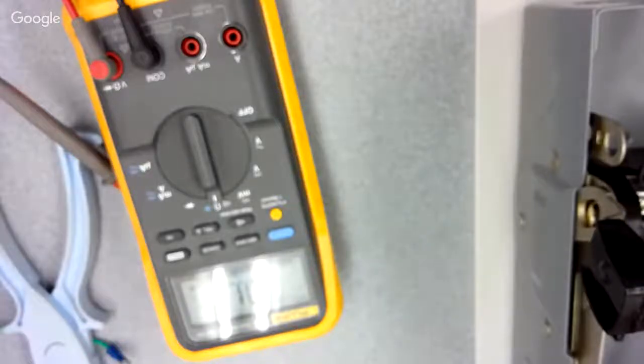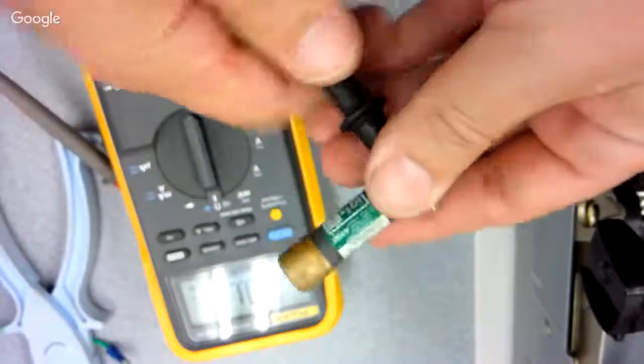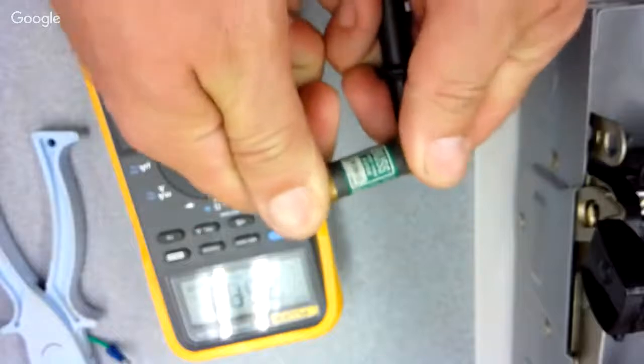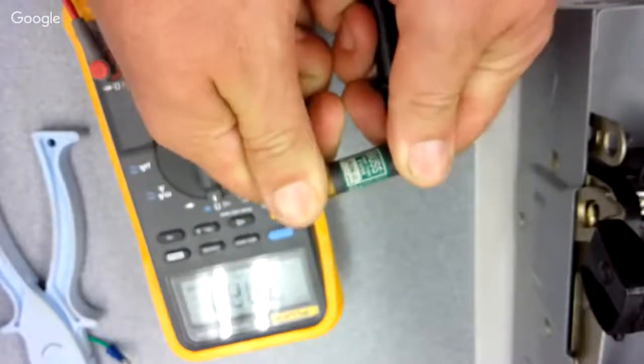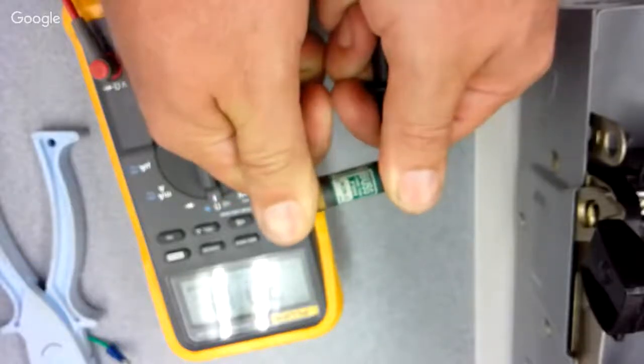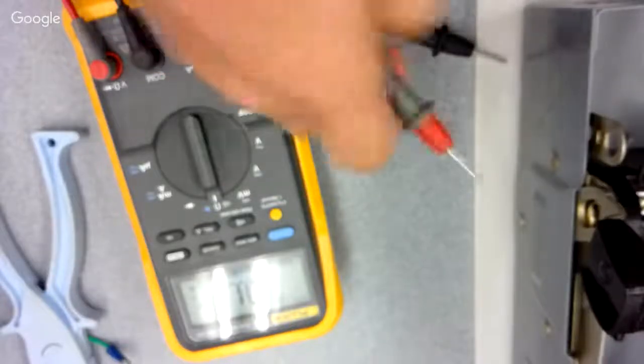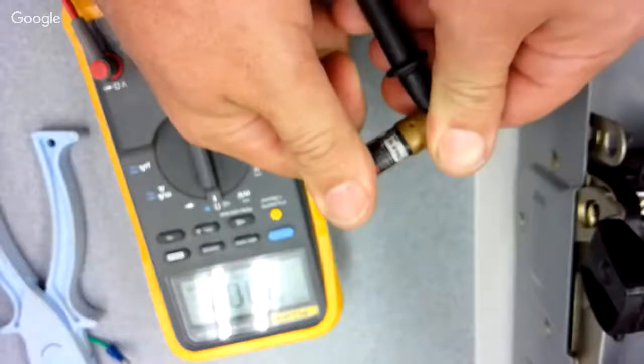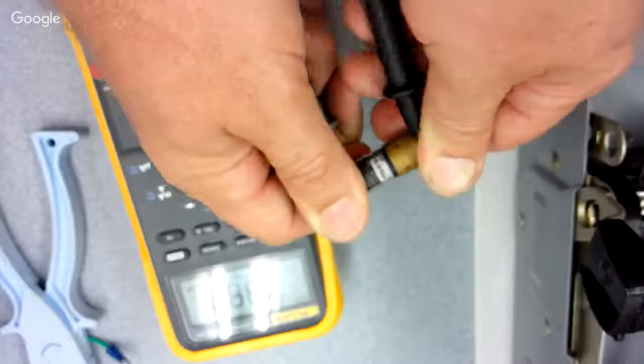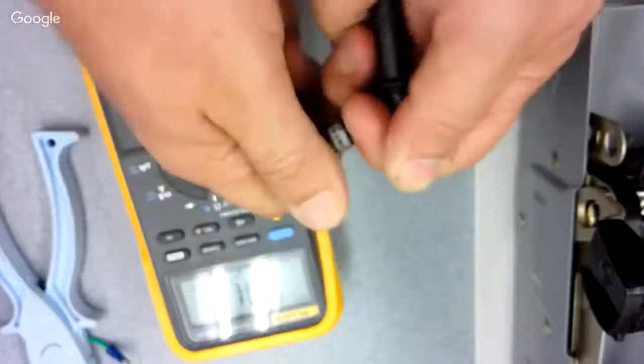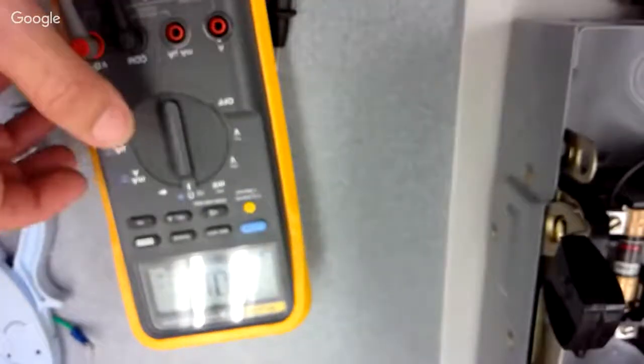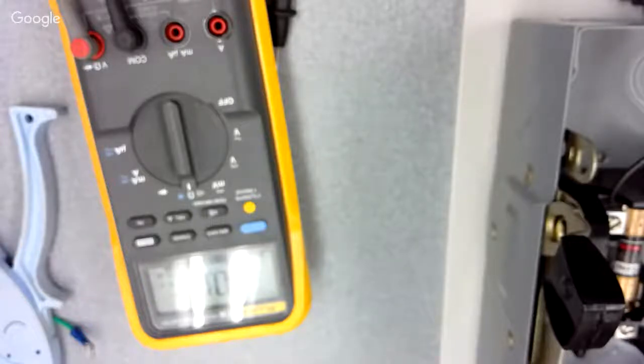If we pulled it out and it didn't test out, so I'm grabbing this fuse and I'm holding nice steady pressure, and I see that it says kilo ohms. That fuse is partially blown or is entirely blown. I don't know why it's not all the way open. We can check another one here. I have a large quantity of blown fuses. See what that one says. That says kilo ohms too. But if I touch my fingers to it, you've got to be careful that you don't actually read the resistance of your body. This should be like 0. This should be just like a solid wire. All right, and so now it's your turn. Go get your meters. I'm going to pause the audio and video.